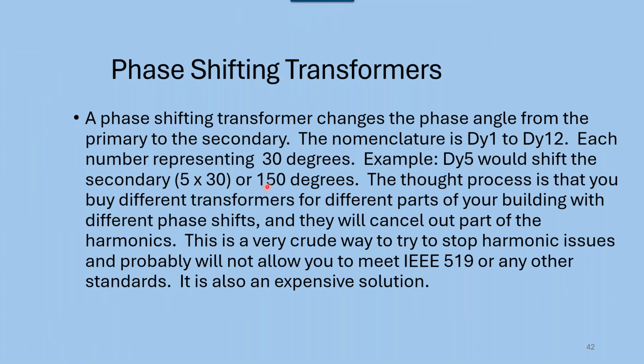So DY5 shifts at 150 degrees. With phase shifting transformers, the recommendation is that in your building you buy DY1 through DY2, DY3, DY4, DY12, all the different numbers, and then you stick them in different parts of your plant. Well, that's great. That's definitely going to help some of the mitigation, just like I showed you on the 24 pulse rectifier. But the problem is they're all over the location. One location may have harmonics, one may not. So you don't really know what you're getting and whether you're complying with IEEE 519 or not. Most likely you're not. This is also a very expensive solution, and I don't recommend it to anybody. It's not a good solution, in my opinion. But I do have one customer that specifies it.